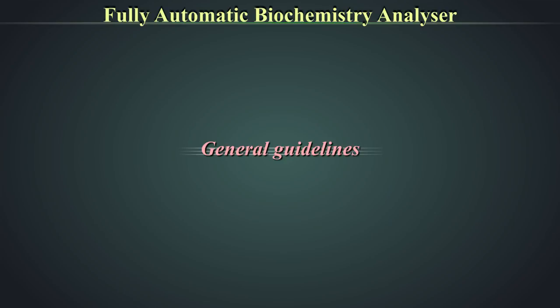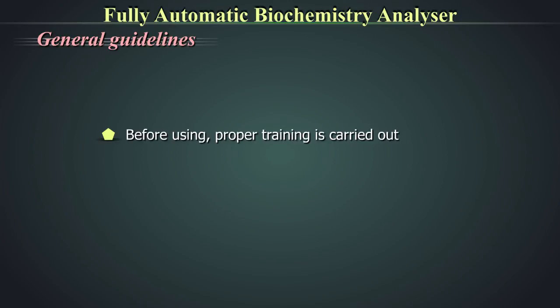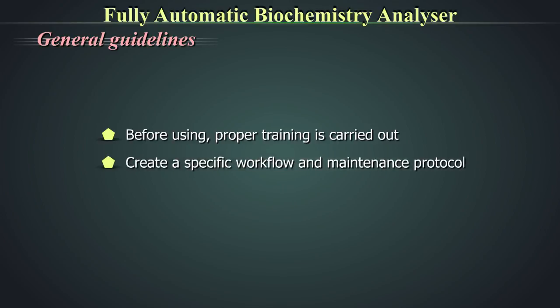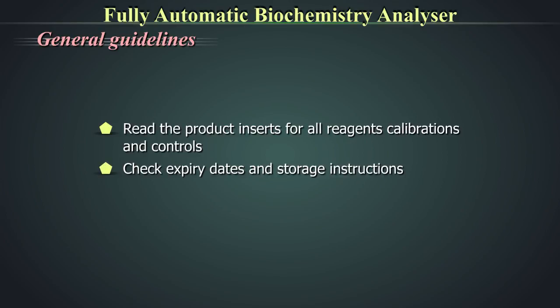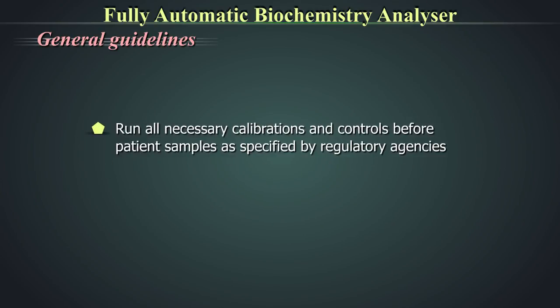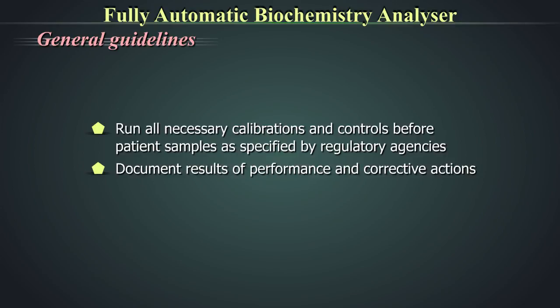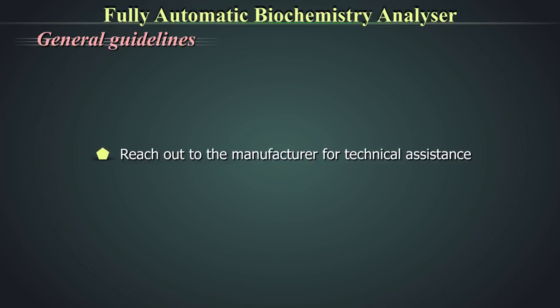General guidelines: Before using an automated instrument, proper training of all users is carried out. Read the user's manual and create a specific workflow and maintenance protocol for the lab. Read the product inserts for all reagent calibrators and controls; check their expiry dates and storage instructions. Run all necessary calibrations and controls before patient samples as specified by regulatory agencies. Document the results of performance and corrective actions taken. Reach out to the manufacturer for technical assistance as required. Please refer to the training module on equipment management.